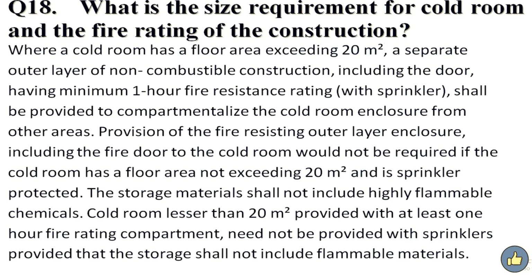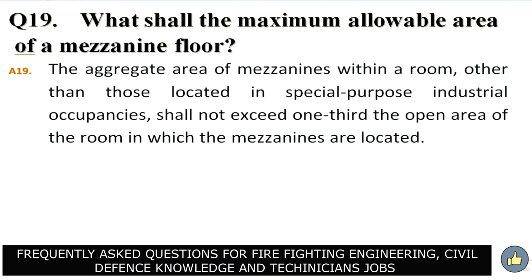Cold room lesser than 20 square meter provided with at least 1 hour fire rating compartment need not be provided with sprinklers, provided that the storage shall not include flammable materials. What shall the maximum allowable area of mezzanine floor? The aggregated area of mezzanines within a room, other than those located in special purpose industrial occupancies, shall not exceed 1/3 the open area of the room in which the mezzanines are located.